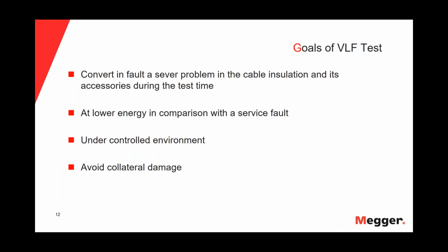The goal of the VLF test is to convert into a fault a severe problem in the cable insulation and its accessories during the test time, and at lower energy in comparison with the service fault. So this is very important, and we will do this under a controlled environment, and we will avoid, of course, collateral damage.